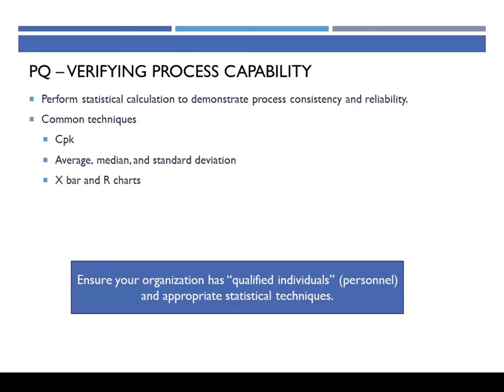And once we do that, then we're going to create a final report that says whether we met our predetermined acceptance criteria or not. Now, if you met your predetermined acceptance criteria, that's great. But if you didn't meet them, be very careful. I know a lot of companies who say, well, we're going to sample 300 pieces and 298 of them have to be good to pass, but we only got 297. And then they say, well, that's close enough. We'll say we met our criteria anyway. We'll write some justification. That's a really bad mistake to make. If you didn't meet your criteria for success, it means you didn't do your homework. You got surprised, and you need to do a failure investigation and a root cause analysis, because otherwise you're going to get surprised again in the future.